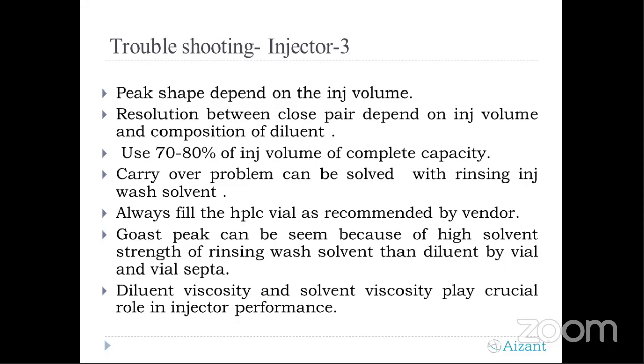Coming to the injector capacity, suppose your system is equipped with a 200 microliter syringe or a 100 microliter syringe, always use 70 to 80% of its capacity. Never try to go to 100%, because if you are using, suppose, 200 microliter, you will face a challenge in linearity. If you're determining linearity of any method or doing calibration, it won't pass. So there is a base guideline that you have to use 70 to 80% of the injection volume capacity. If you're using 200, then at most you can go with 150 or 160 microliter instead of directly going to 200. The higher end will always be a challenge.